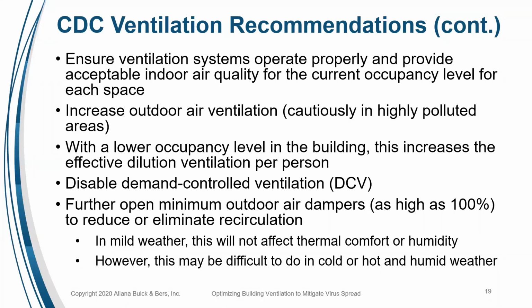Also, you want to open outside air dampers as much as possible. You want to reduce the amount of recirculated air in the building. You won't recirculate as much, and will bring more in from the outside. But obviously, this is going to be very dependent on the climate conditions and where you're located.